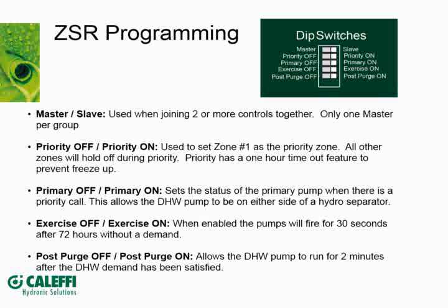The primary on, primary off. During a priority call, you have the option to either run the primary pump or not run the primary pump. The reason you would want that is, let's say you had a hydro separator in your system and you put your indirect on the secondary side of the hydro separator. That priority pump would be running, but you're going to need the primary pump to run as well to get the water over to the boiler. So you could set it up that way if you want. It just gives you a little bit more flexibility.